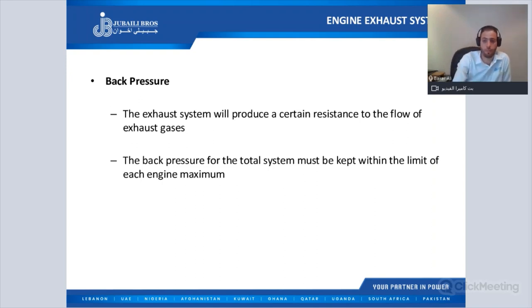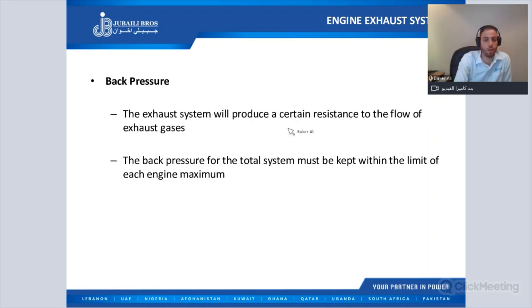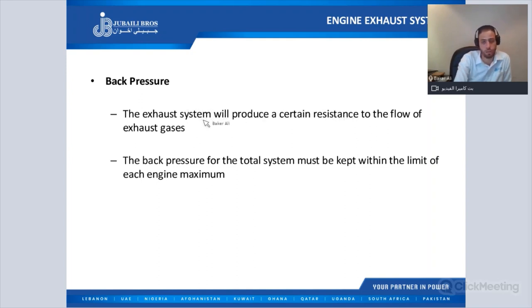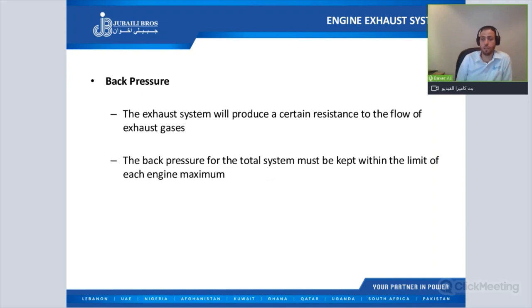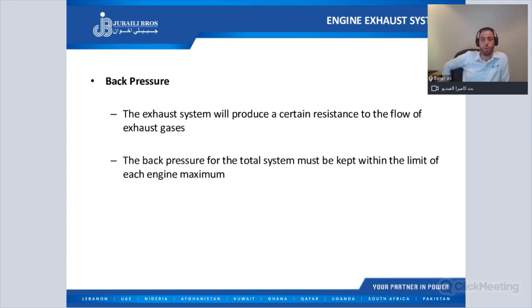Now we'll talk about back pressure. The exhaust system produces a certain resistance to the flow of exhaust gases — this is called back pressure — and this back pressure must be within the engine's maximum limit. For every engine there is a maximum back pressure allowed, which we can find in the data sheet provided by Perkins. Our exhaust system's back pressure should not exceed this number.